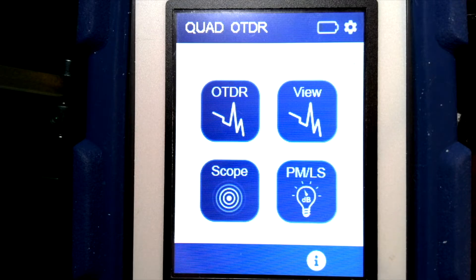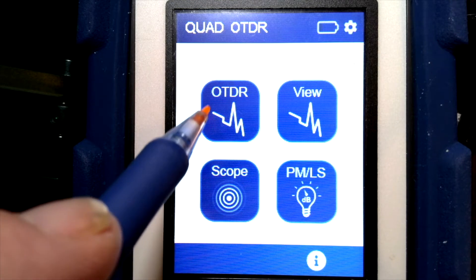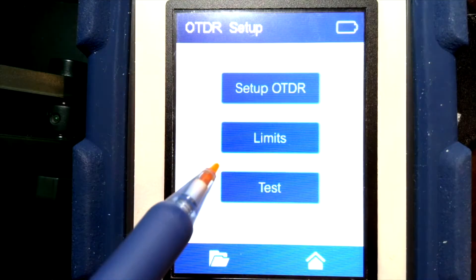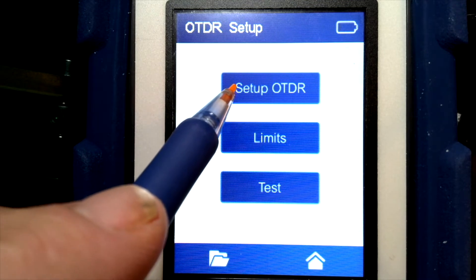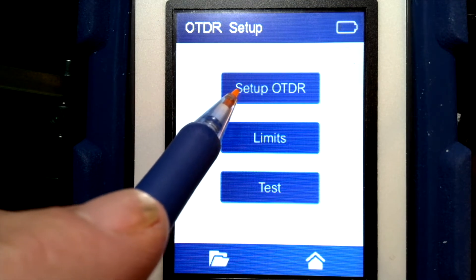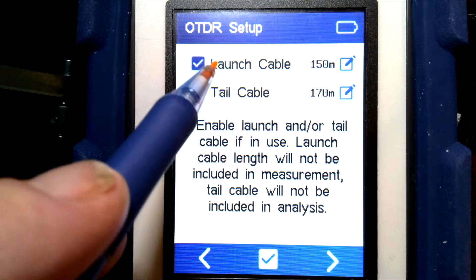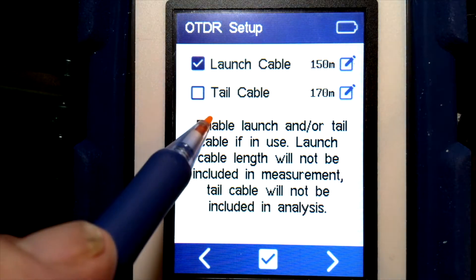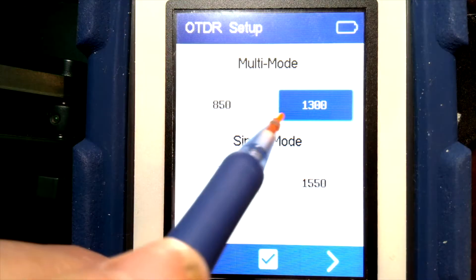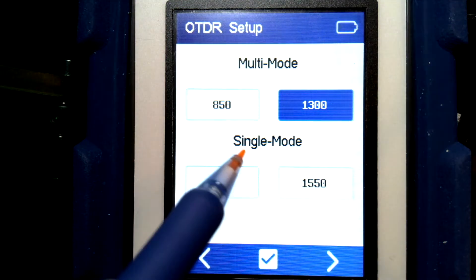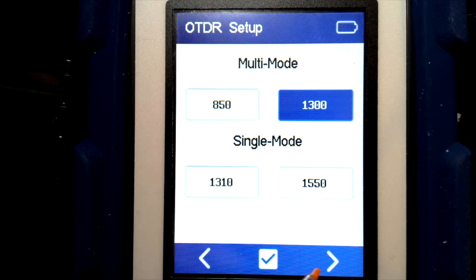Let's take a quick look at the overview of how the OTDR is set up and run. If we go into the OTDR setup screen, we have the configuration options which adjust the acquisition settings. This lets us choose whether we have a launch or tail cable selected, and we choose our wavelength — we can choose both wavelengths or one wavelength for each mode.